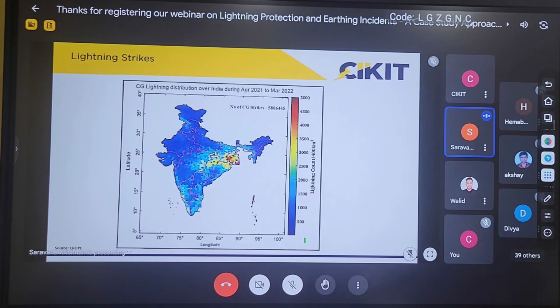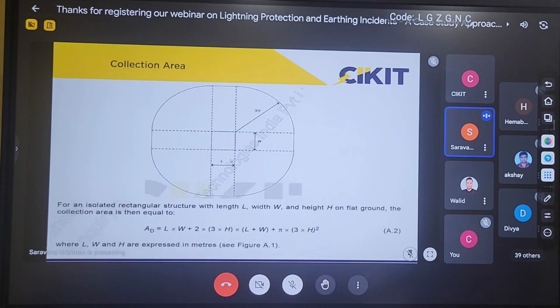So this is the collection area. While performing the risk assessment calculation, I won't consider the dimensions of the building alone. Based upon the dimensions, the area outside the building also has some influence. The area up to which the building or structure has influence is considered the collection area. If you closely observe, the slope is considered as 3 times the height. So if the height of the building is much higher, then the area covered will be much higher, and hence the risk due to lightning will also be much higher. So practically and theoretically, the height of the building plays an important role in the risk assessment.